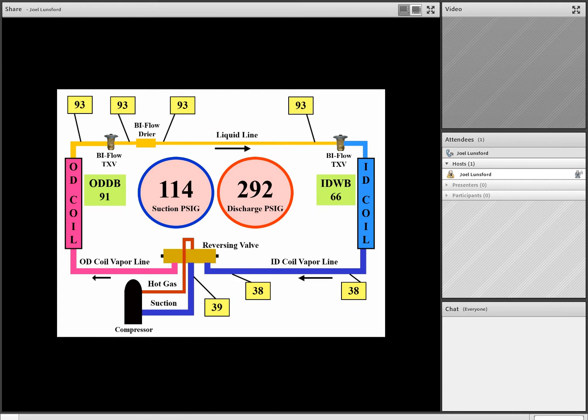Good, whoever said low heat load. If we have a low heat load on the cold coil, in other words, if we have inadequate airflow on the cold coil for whatever reason, it's going to drive the suction pressure low, the liquid pressure low, the superheat low, and the subcooling low.